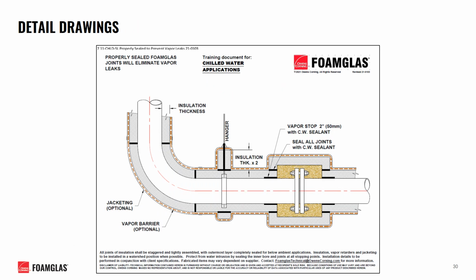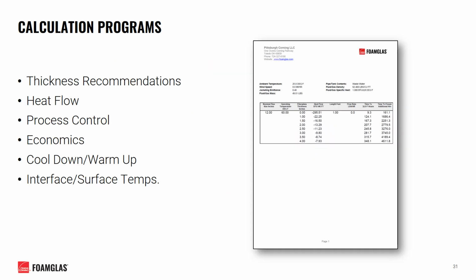Here's an example of one of our detailed drawings that we offer, specifically for our chilled water system. We generate drawings like these regularly to help bridge the gap between specification and field installation, and to increase the confidence level that proper application techniques are being utilized on site. We maintain and utilize a full suite of proprietary thermal calculation software to help aid in the design for those who specify our insulation systems. If you have questions as to what insulation thickness or jacketing material to use in order to achieve a certain surface temperature, if you're curious about cost savings potential, or have general questions about process control, we'd be happy to assist with a thermal calculation report tailored to your specific system.